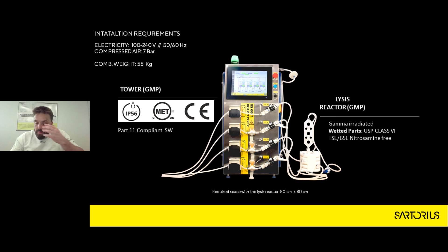The GMP version of the tower is IP56, so it is dust protected and water resistant. It does have cUL for North America, it also has CE for Europe, and the software is Part 11 compliant, meaning in the GMP world you have all the audit trails, the traceability needed for a GMP environment, the alarms, the interlocks, yes, all the needed stuff for the GMP environment.